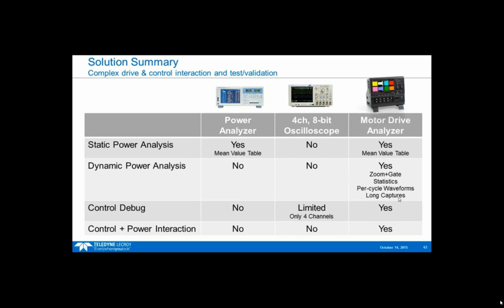They have really long continuous captures, statistics, and also the ability to use the zoom and gate capability, plus the control capability. With this product, especially in 2-wattmeter mode, you get 4 other channels you can use to look at control signals and verify everything is correlating the way it should. You have no ability to do that on a power analyzer, and with a 4-channel scope you have limited ability but can't do anything with the power analysis. So this combines everything in one tool, making it easy to see the control and power interactions as we described in that example.